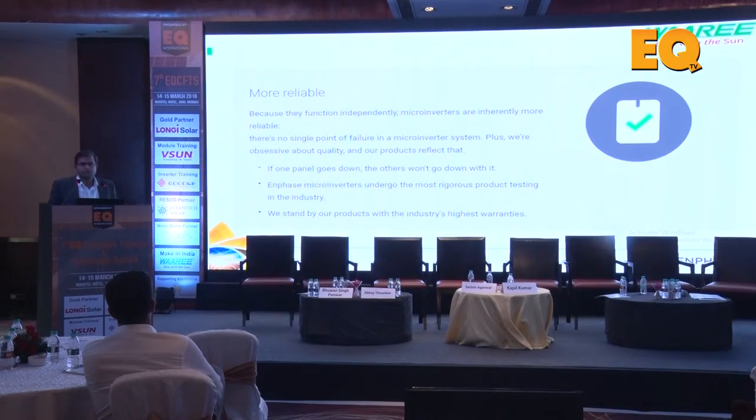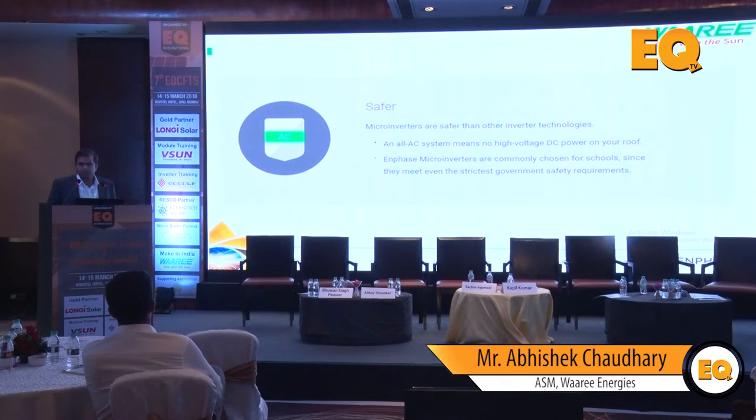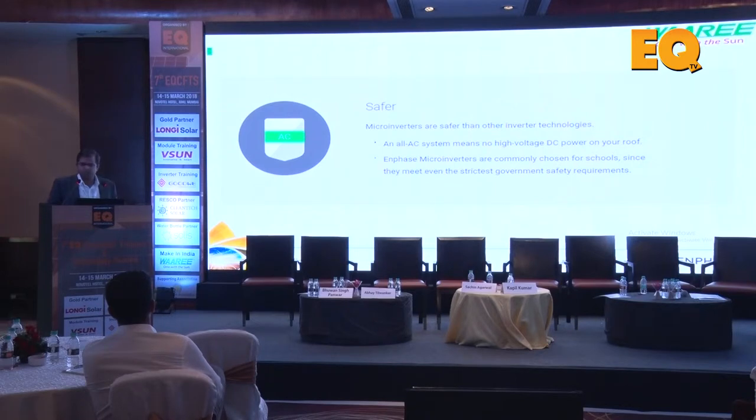The infant mortality rate of these systems is already taken care of - you will never get a faulty system because you have more than one million hours of testing done from the factory itself. Safety is a key concern: 800 to 900 volts of DC wiring running on top of a building - customers don't really understand it, and integrators don't educate customers about it. If you look at the Chinese market with much higher installation numbers, DC fires cut through sheet metal like butter. Many integrators use less than optimal MC4 connectors and don't really understand how crimping is done.